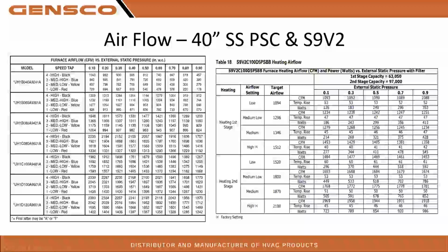So we're going to compare that. We're going to get an old 40-inch furnace. This is a PSC chart. This is a newer S9 V2 chart. And so once we pull that static number, we know, like on this example, we'll pick an upflow 80,000. We're going to go, okay, we're on medium high, we're on blue. I had a 0.5 static, a perfect 0.5 static. I'm moving 1280 CFM. So we're doing the math for you, right?